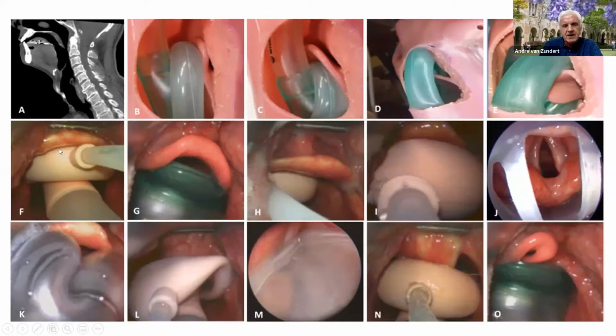So we need to be careful. Visualizing the technique, make sure that we see that the device is the correct size and sits correctly. I've explained to you that there is a possibility of air leakage due to the lack of an inflatable cuff. This is a silicone device. The cuff is made from silicone, which results in a nice deployment of the device, whereas PVC not always results in the same deployment, and that can be a cause of air leakage.